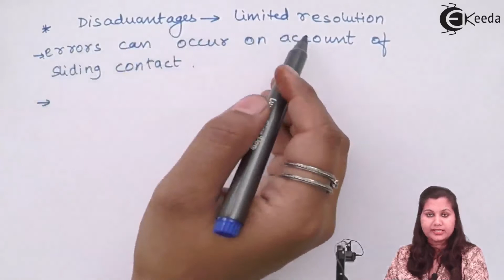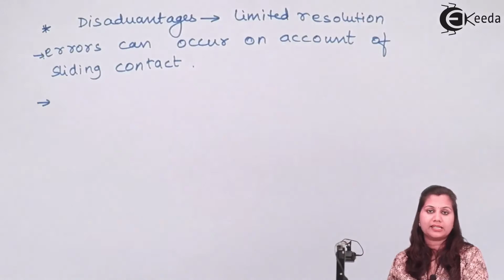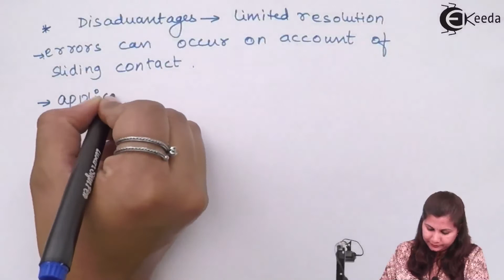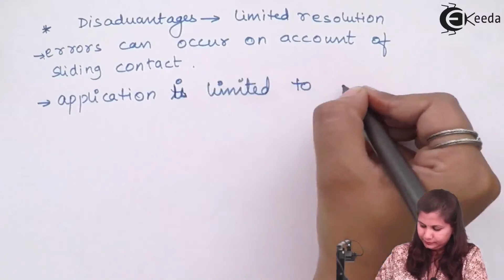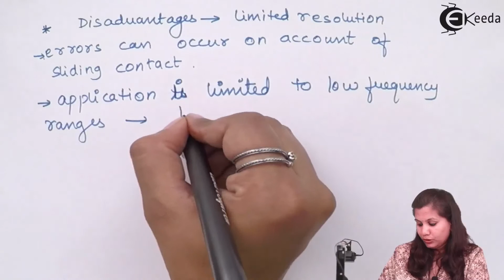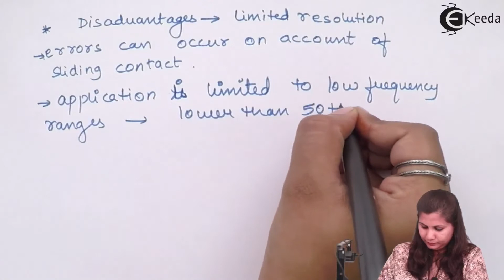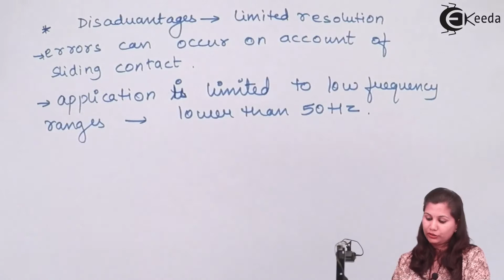This limited resolution is provided, and generally the resolution is good only at very low frequencies. Due to this disadvantage, the applications of this potentiometric accelerometer are limited to very low frequency ranges, lower than 50 Hertz. So this type of potentiometric accelerometer is useful for low frequency applications only, and its disadvantages are that it has very limited resolution, and errors can also occur due to the presence of the sliding contact.